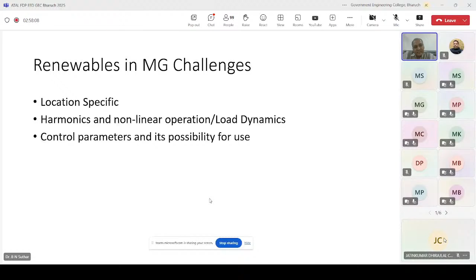RES generation may not be transported over a longer distance in real and reactive power, but it can be transferred with certain constraints. When we want to transfer reactive power over a longer distance, it is very difficult. First, it cannot be transmitted alone; if you want to transmit reactive power, it has to be done with some amount of real power, then it becomes possible. And transmitting reactive power over a longer distance also creates stability issues, voltage fluctuation issues, or voltage regulation issues.